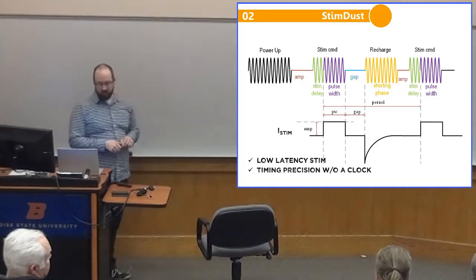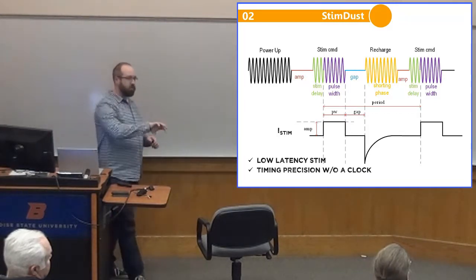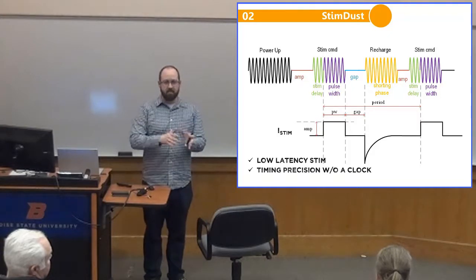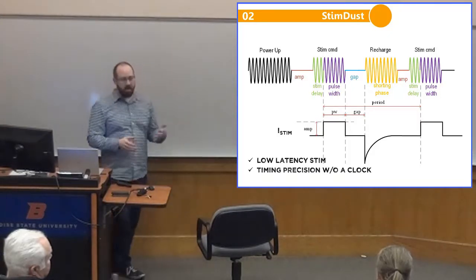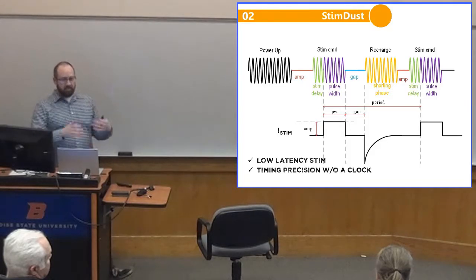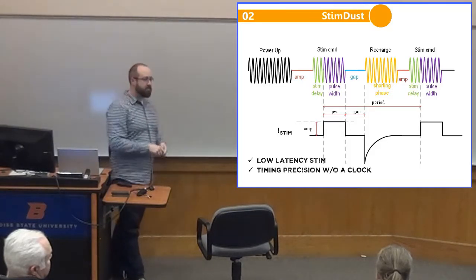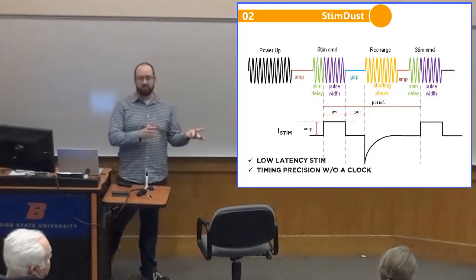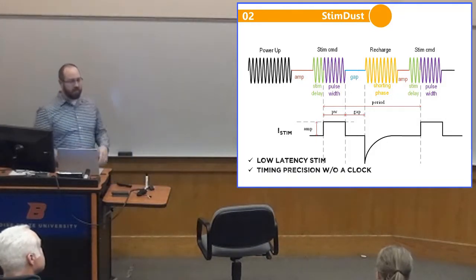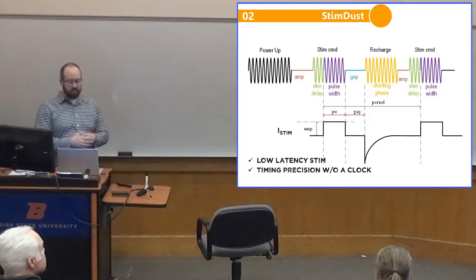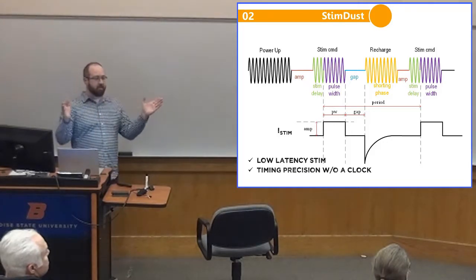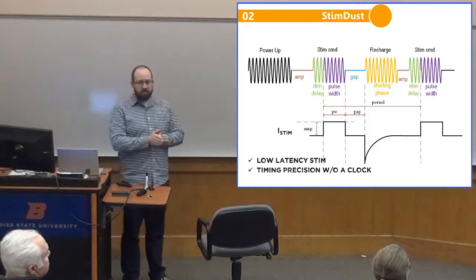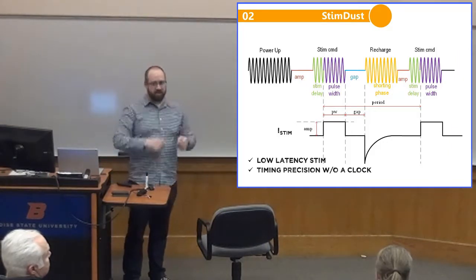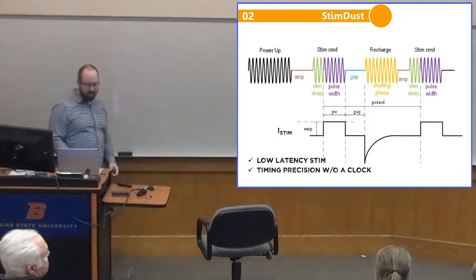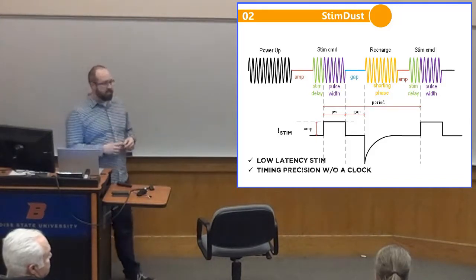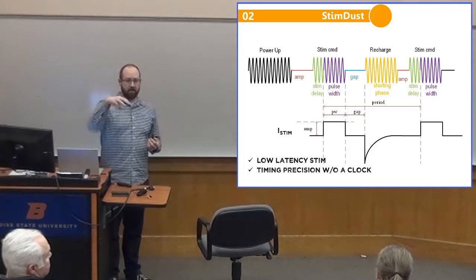In terms of what the system does, it uses the external ultrasound protocol to deliver precise stimulation charge. After a power-up sequence, there's a gap, and the length of that gap programs an amplitude for stimulation. So rather than being dependent on the received power, we can precisely control the pulse width, the gap, and the period just by altering our protocol—leaving the ultrasound on longer or shortening it—to deliver different stimulation patterns. Overall, we have low latency stimulation, and timing precision without an on-chip clock.